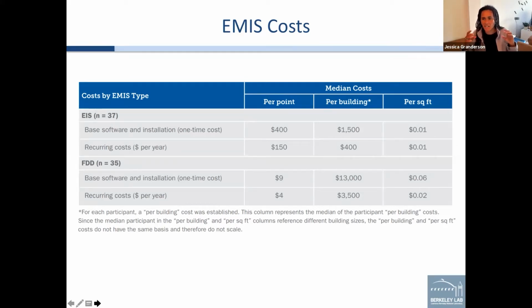There's a lot less data being fed into the meter analytics tools, and a lot more data being ingested by the fault diagnostics tools, which look at all the control system data - orders of magnitude differences in the number of points being analyzed, integrated, and maintained. You see that reflected in the per-point and per-building costs between that top row of meter analytics and EIS, and the bottom rows on fault diagnostics.